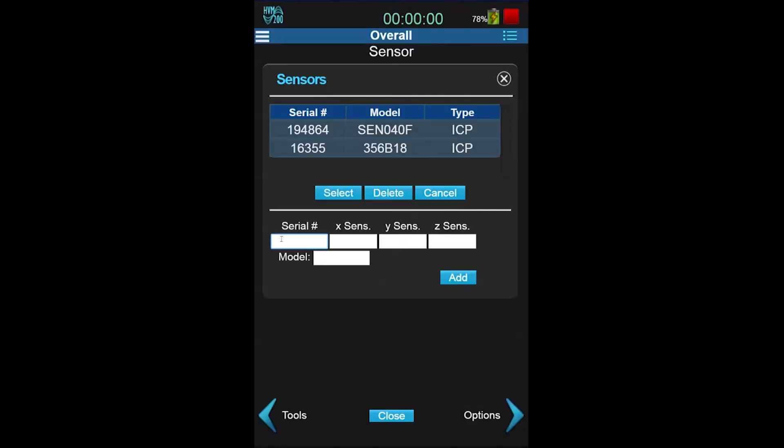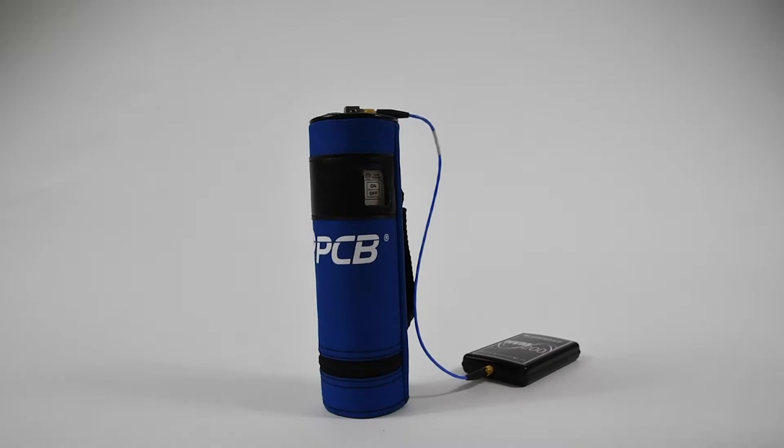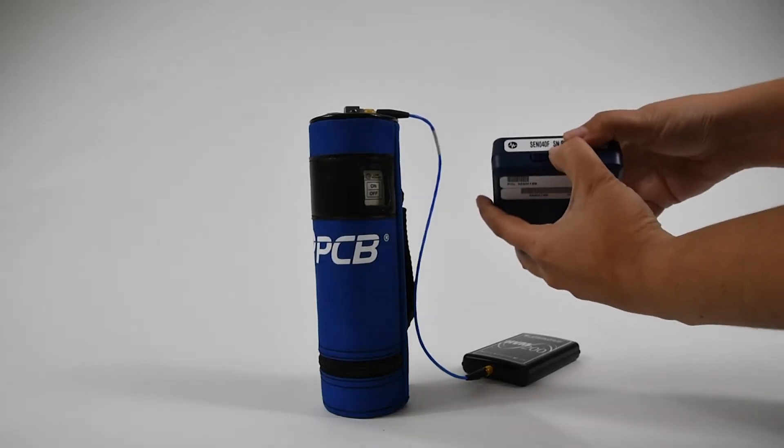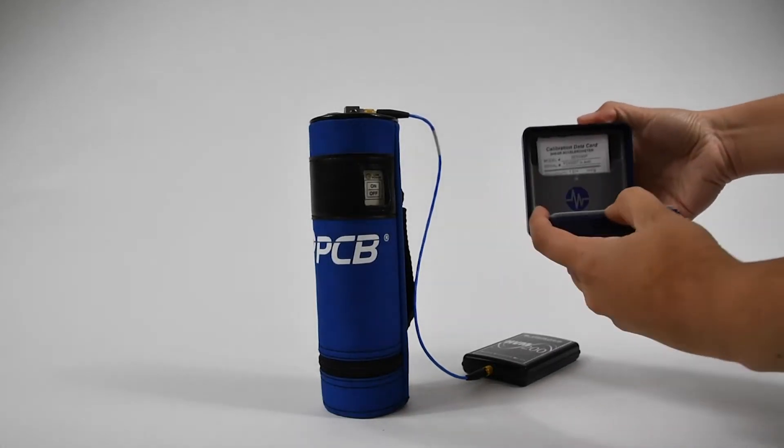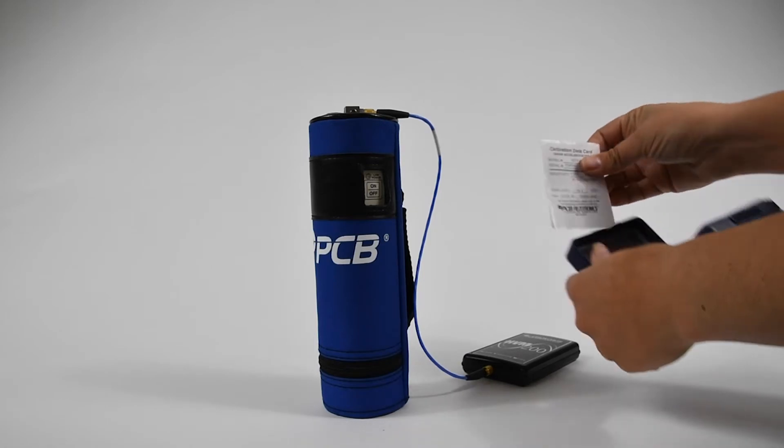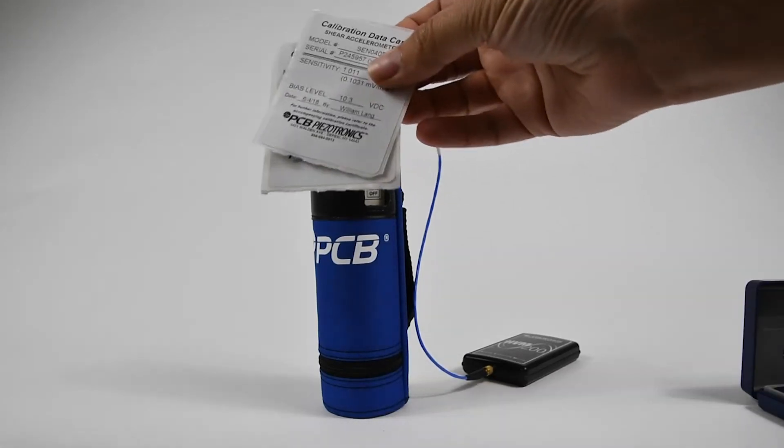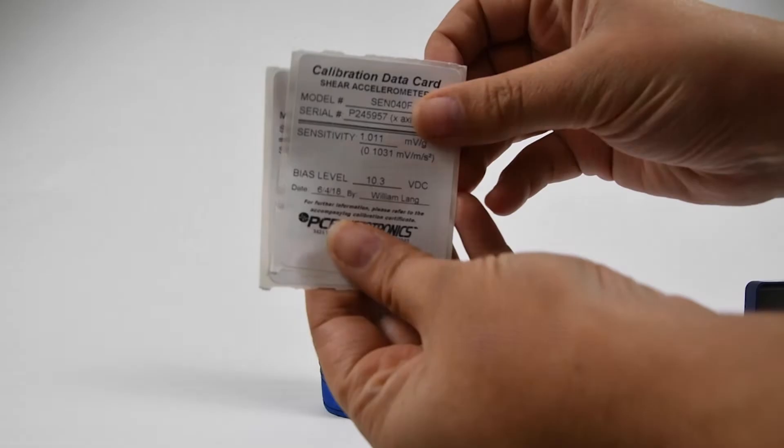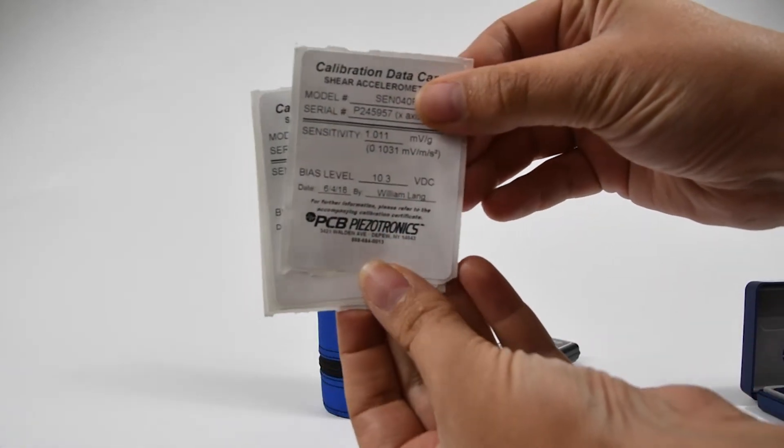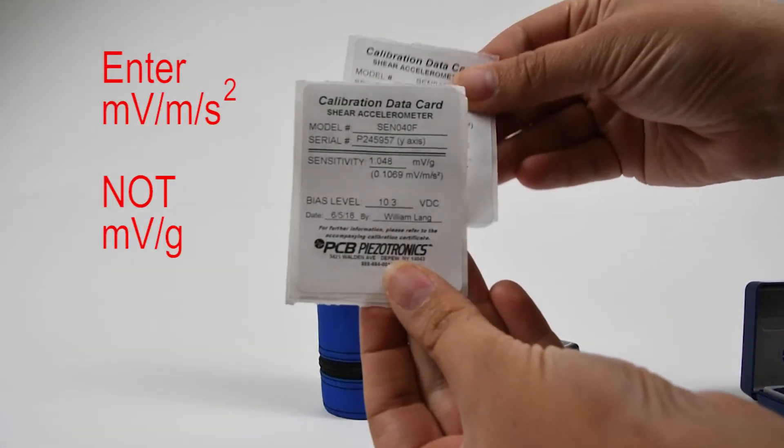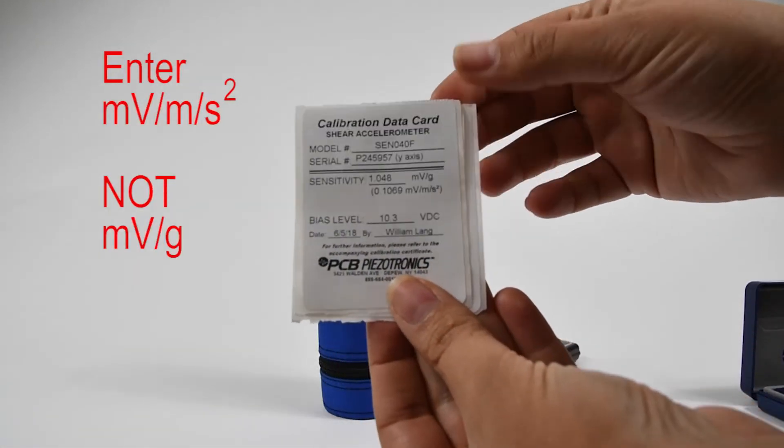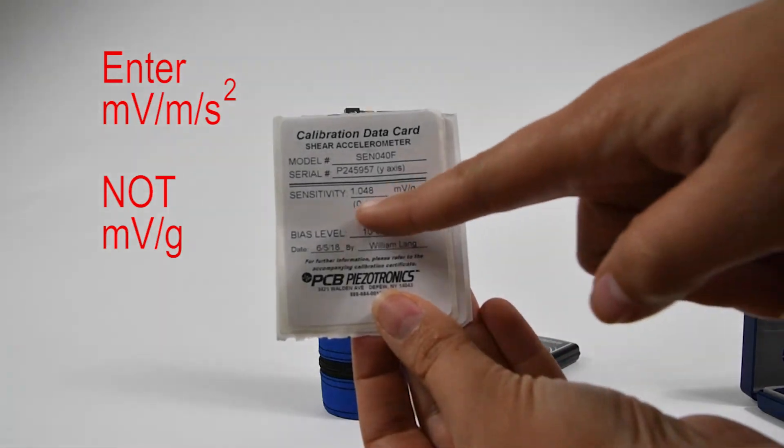If your sensor is not in the list, then enter the values here. The sensitivity for each axis can be found on the paper inserts inside the box. Enter the millivolts per meter per second squared and not the millivolts per g.